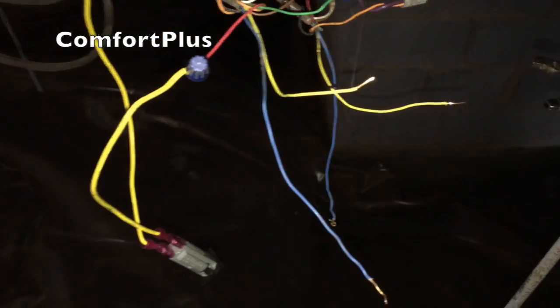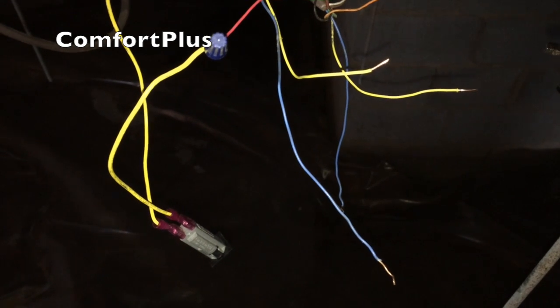Okay, I cut loose the compressor, the yellow lead going out to the outdoor unit, and had the same amps, so I took the reversing valve loose. But the amps went away when I broke the blue wire. So I'm thinking that the wire may be damaged or something wrong with the defrost board itself. So I'm going to go out to the outdoor unit at this point and investigate this blue wire.